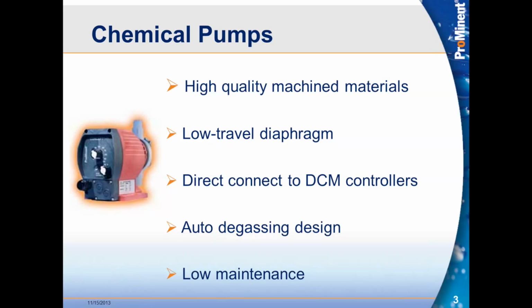Whereas our pump has more of a squish. You hear a fluid moving through the pump, and it's not anywhere near as loud. And that low travel diaphragm means less wear on the diaphragm and a longer lasting diaphragm. We also have an auto degassing design, which allows us to not need a 4-function valve. So we have one less moving part, one less accessory that we have to add to our pumps.